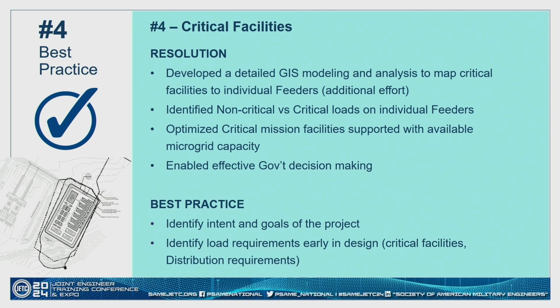We had to identify the non-critical and critical facilities on each feeder and optimize what we could power with the generation specified in the DD1391. We only had 10 megawatts—that's all we had. We also had some PV, but you can't rely on it for everything since it's not available 100% of the time. We came up with a large number of scenarios and gave them to the government with our recommendation. It went to the base commander to make the final decision—that's where it goes. Somebody has to say thumbs up or thumbs down.